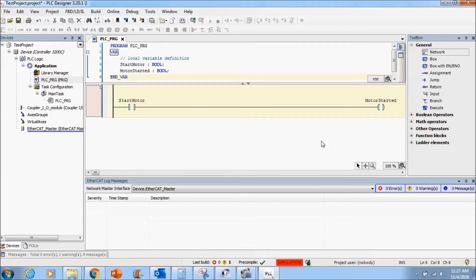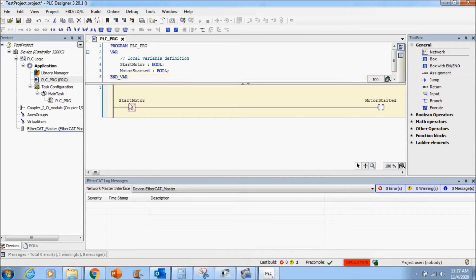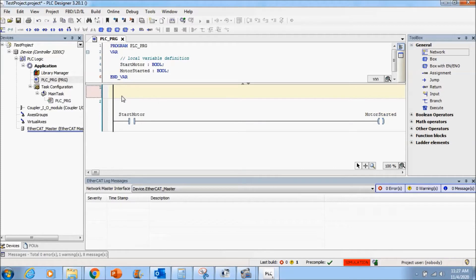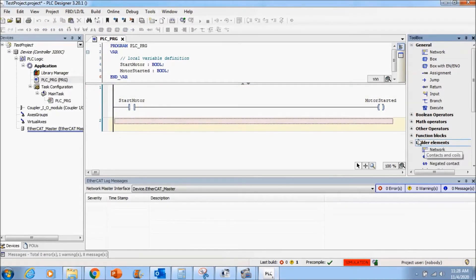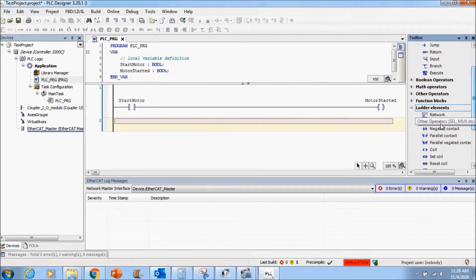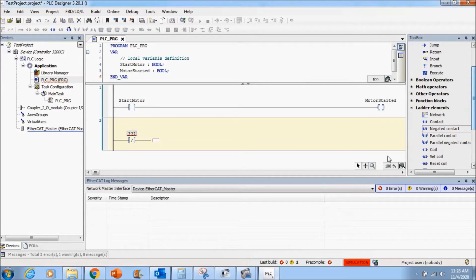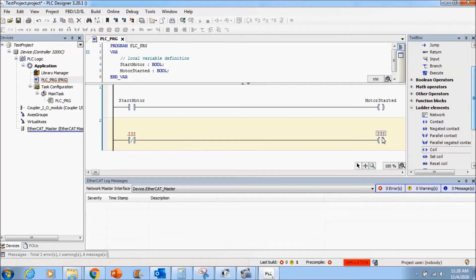What is bit logic? Bit logic includes, for example, normally open and normally close contacts, sets and resets, and so on. Now we have a normally open contact and let's add here one more network. We can add below, and in the elements area I will add a negated contact — or normally close contact — and with drag and drop we can put our coil here.